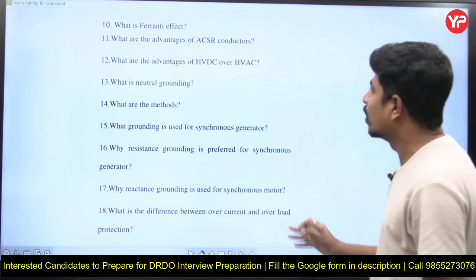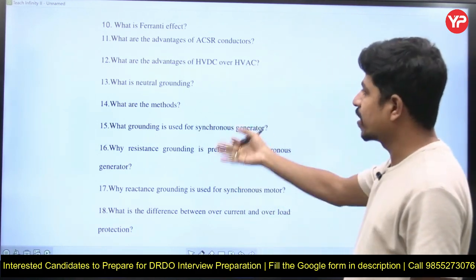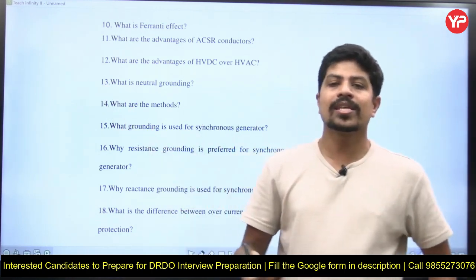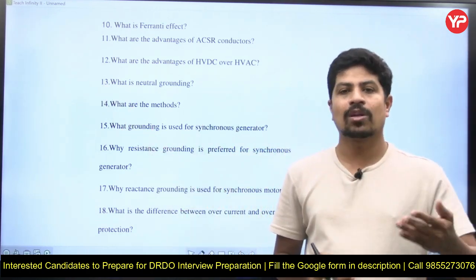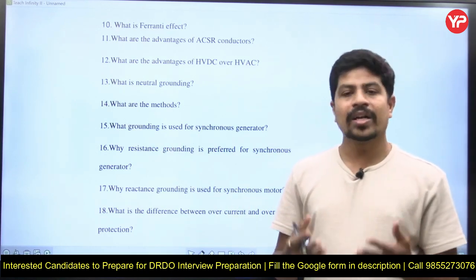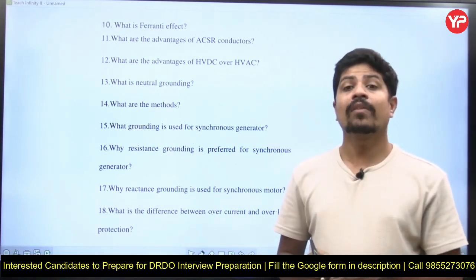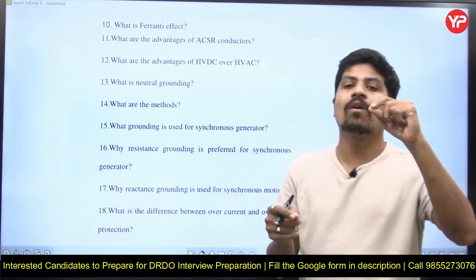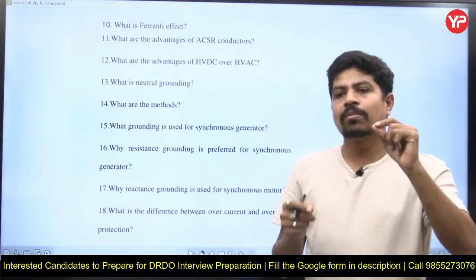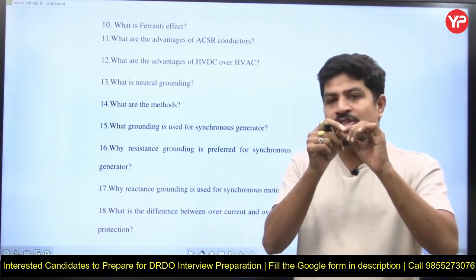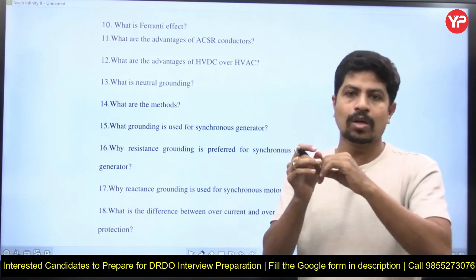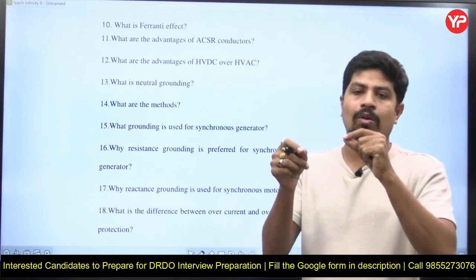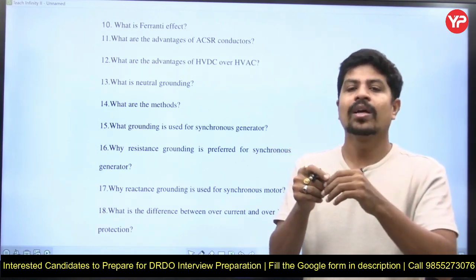The advantages of HVDC over HVAC question came up repeatedly. Next: what is neutral grounding? They may also ask the difference between neutral, earth, and ground. For a three-phase machine like a transformer or generator, if it is star connected it has a neutral point. Connecting that neutral to the ground is called neutral grounding — not earthing, which is a different concept. There are several methods of neutral grounding: resistance grounding, reactance grounding, and Peterson coil grounding.